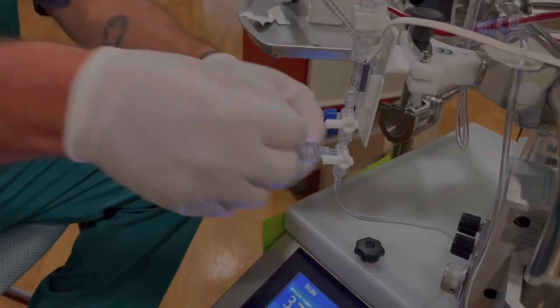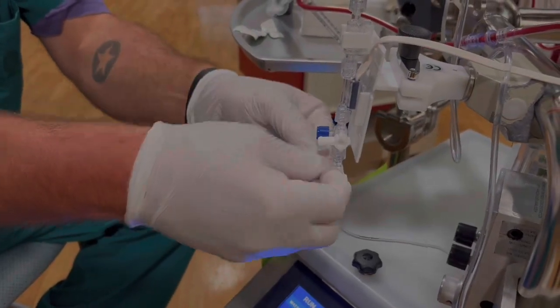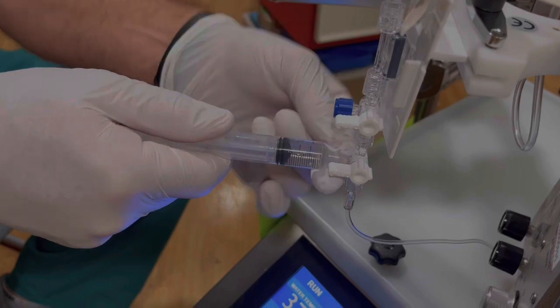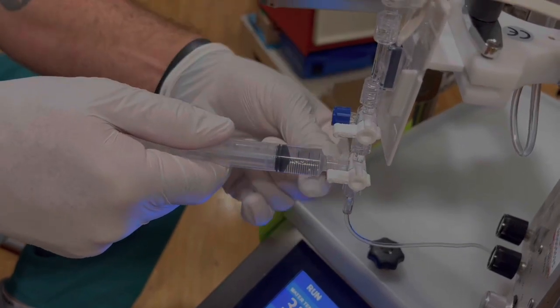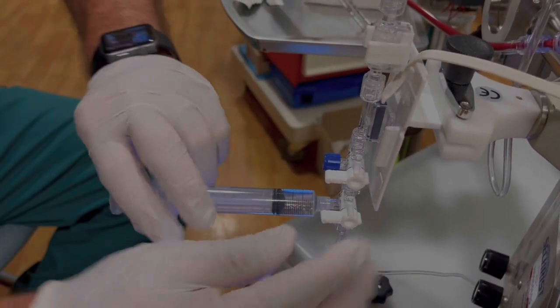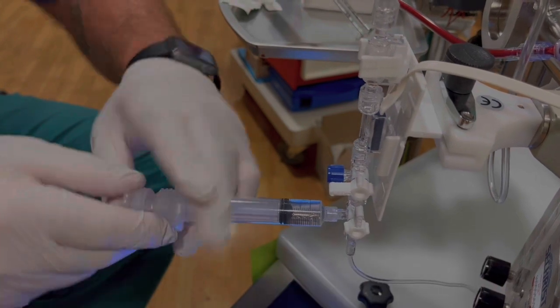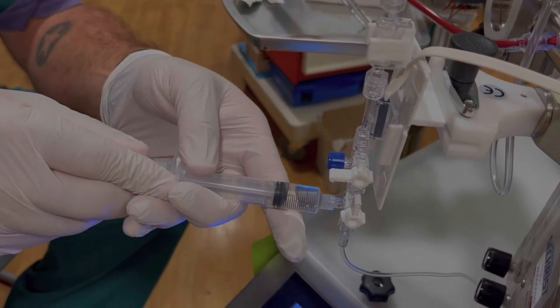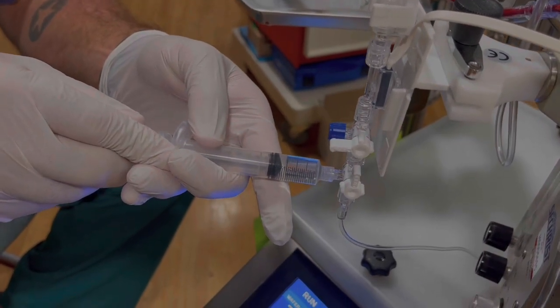We're going to zero our post-membrane transducer on the Spectrum CP22 pump. As you see, the first step here is to clean our stopcock, our access point. Then we're going to open up to the circuit with our hand on the plunger, as this is a high-pressure system, and aspirate the syringe.